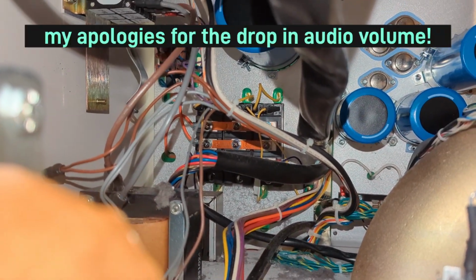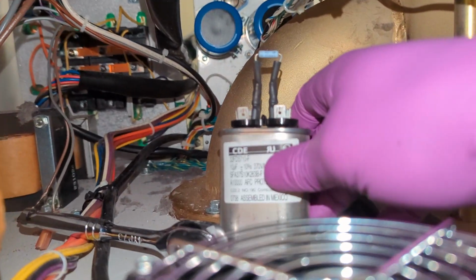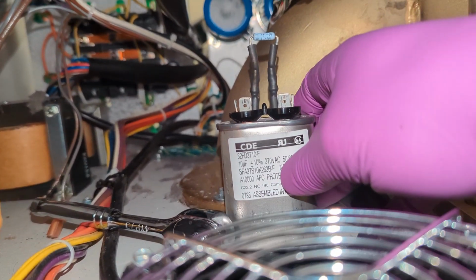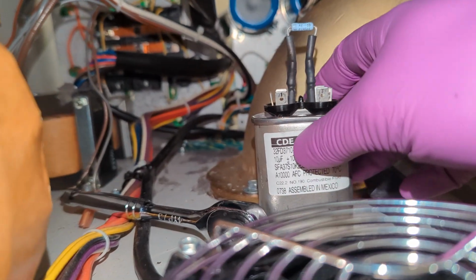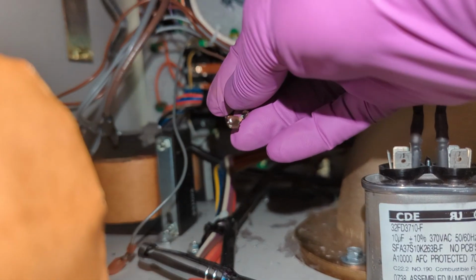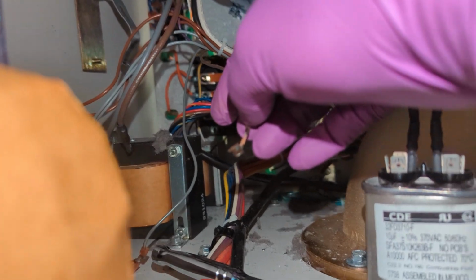All right, so we're looking through the back of the centrifuge, and that is the main power switch. So you've got line voltage going in, load coming out, and so you've got these two, your live and neutral connections, which connect to this capacitor. Okay, this 10 microfarad cap, and then of course you've got additional neutrals and live wiring on the load side. And look at this. Sorry, my camera.